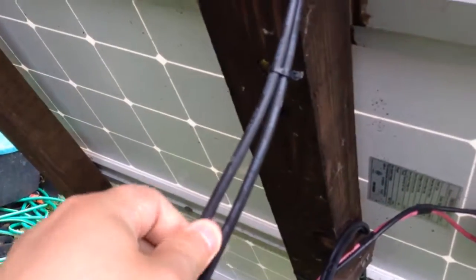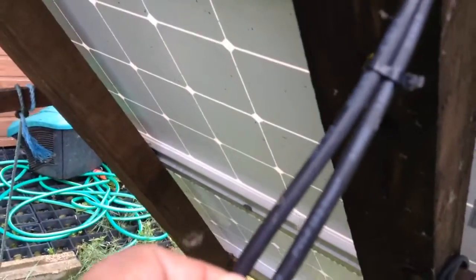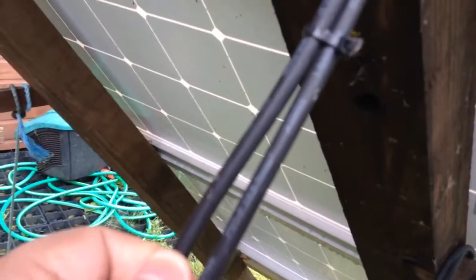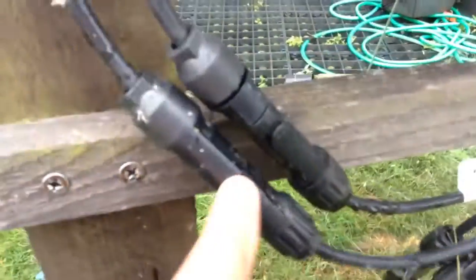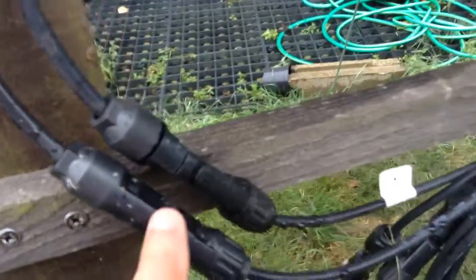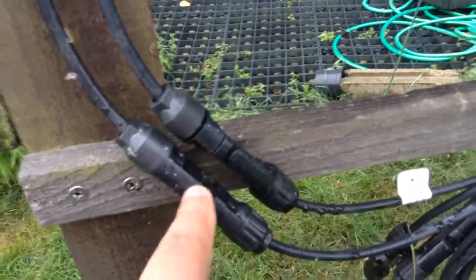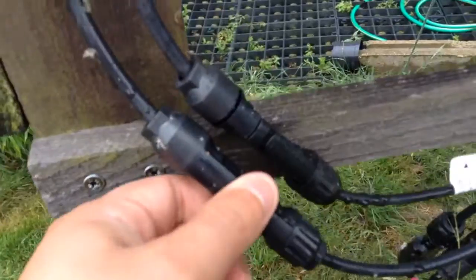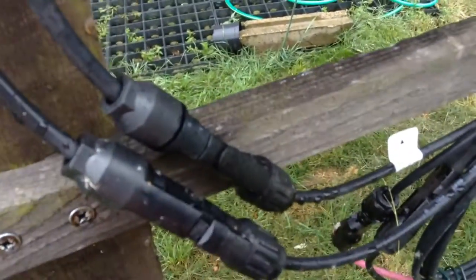The panels come with leads fitted - this is outdoor solar PV cable. The cable connected to the panels is 2.5mm squared, though for any longer runs I would use the 4mm squared cable, and they have waterproof connectors on. These connectors are called MC4, I believe it stands for multi-contact 4. These just clip together and are fully waterproof for outdoor use.